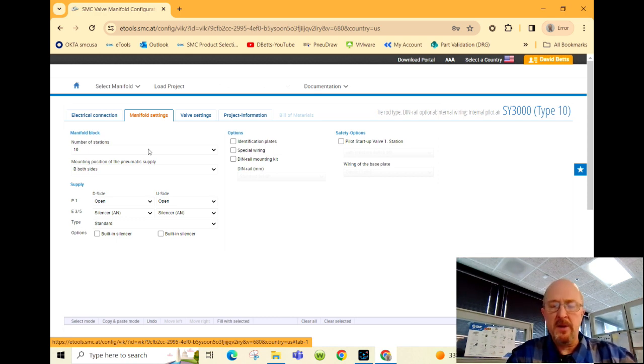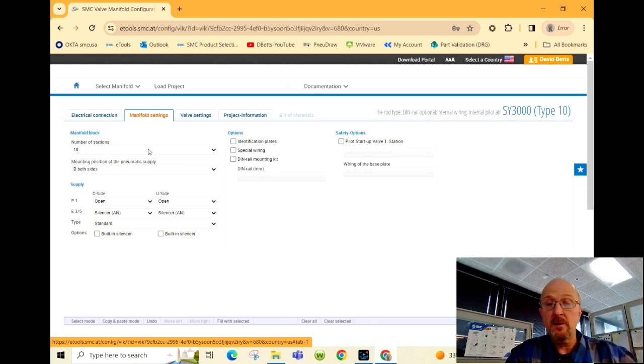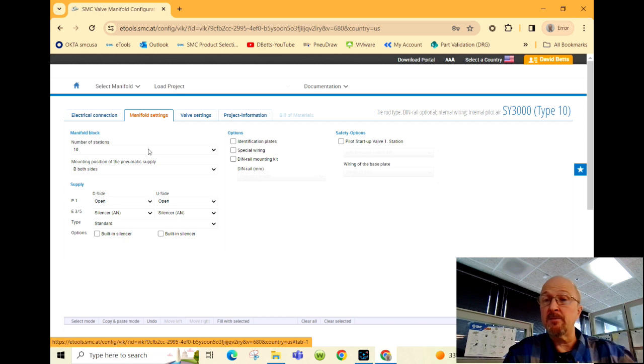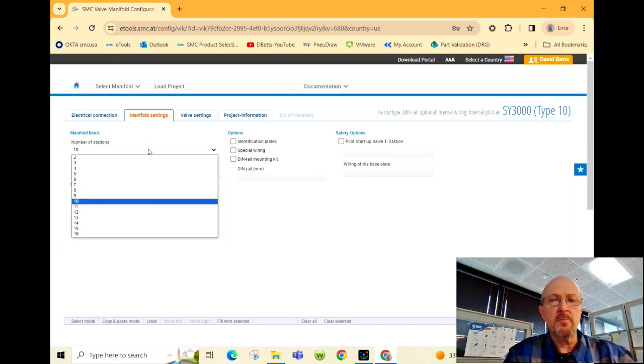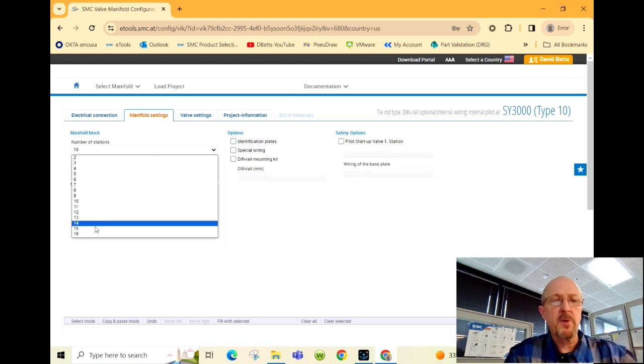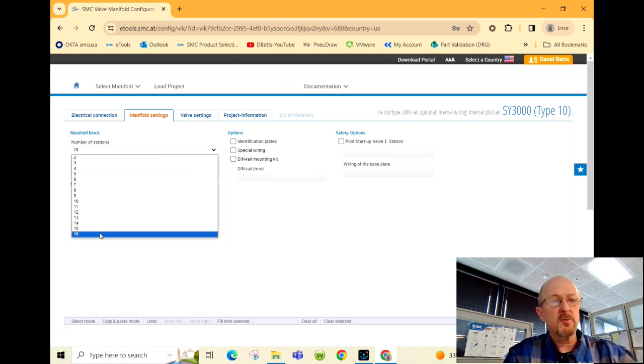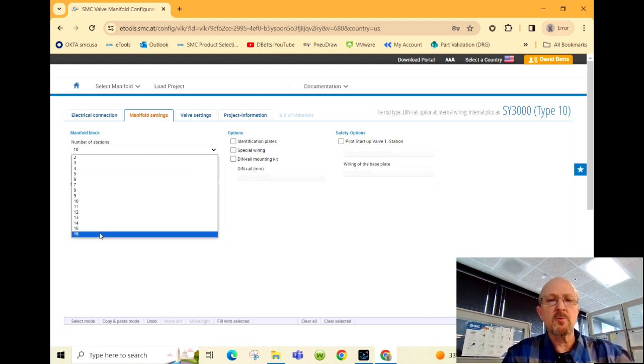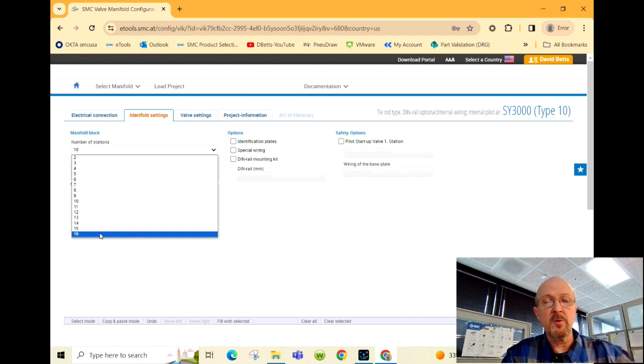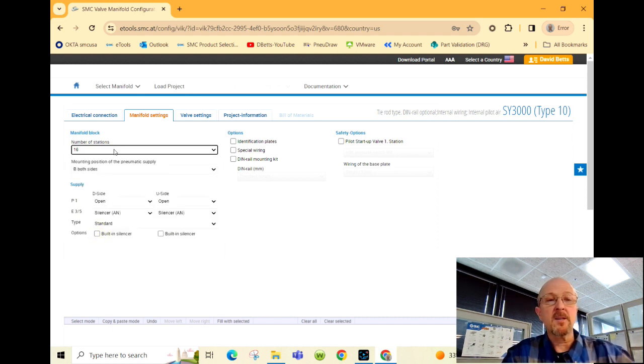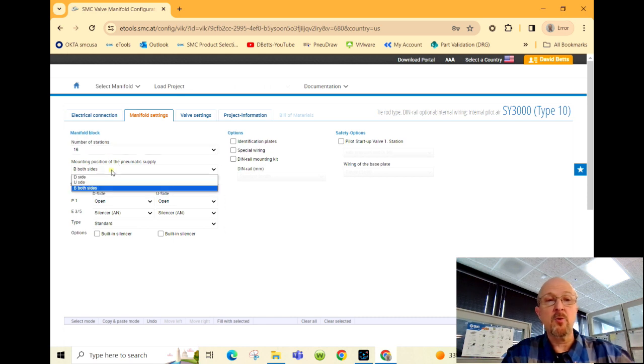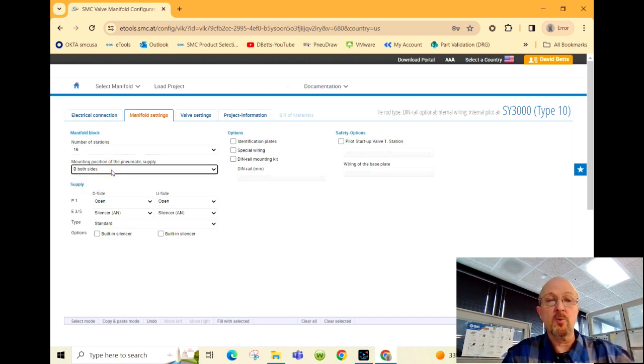The manifold can be expanded once you receive it in the field, but we do encourage you to build in some expansion capacity. This particular customer was looking for a number of manifolds, so I'm going to build a 16 station first. Anytime it's over eight stations, we always recommend bringing the pneumatic supply to both sides of the manifold.